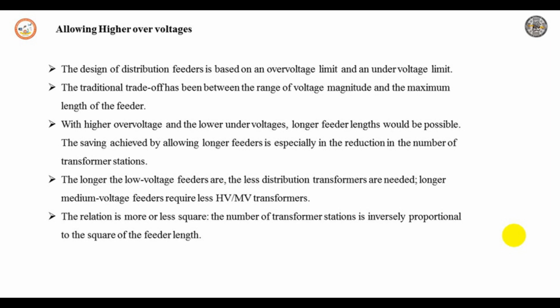This would most likely reduce the hosting capacity, because the location with the lowest over voltage margin would be further out along the feeder. Allowing higher over voltage and lower under voltage would thus not automatically result in more distributed generation being able to connect to a feeder.